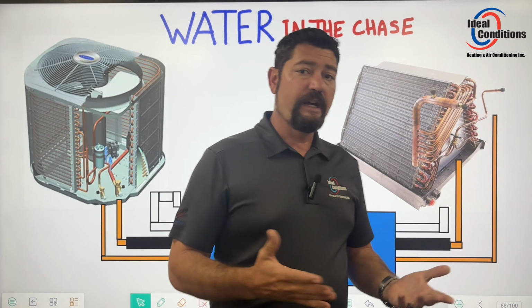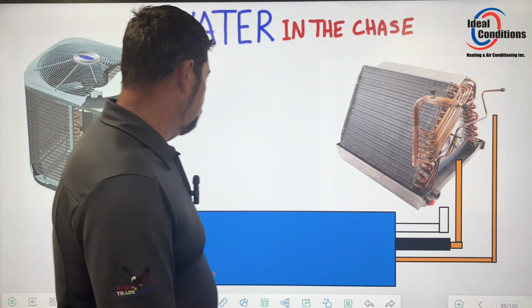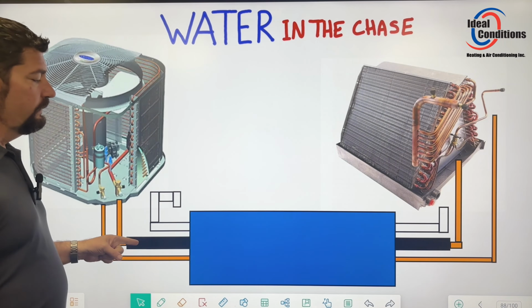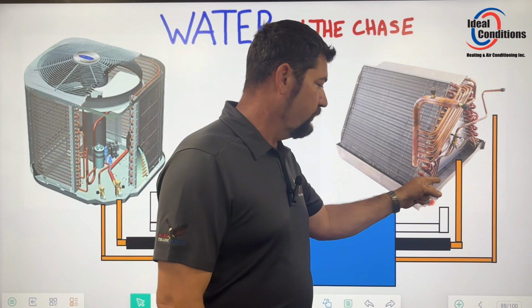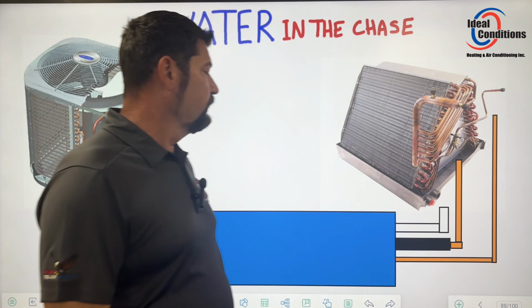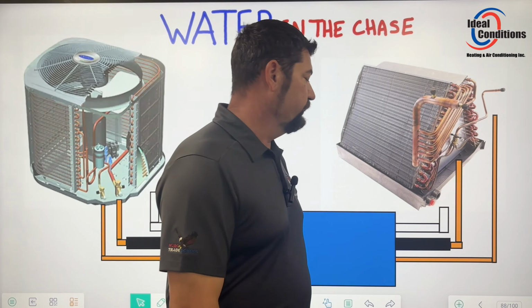it's that nobody's checking to see what my superheat is, and if I'm starting up and I have a good superheat on startup, it's probably because that water's not been chilled down, because there's been no fresh condensate water added to it, or these pipes chilling that water down. So, I mean, it's almost acting like a chiller barrel in a way.